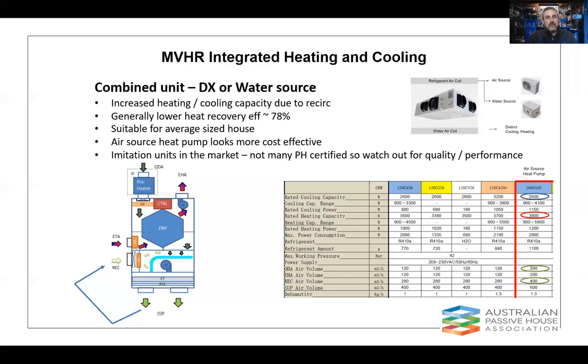Typically these products are not at the upper end in terms of heat recovery efficiency. So the unit is an all-in-one, designed to be multifunctional. Obviously with heating and cooling, the efficiency for a broad application becomes slightly less critical. But in the passive house market, equally, we're still looking ideally to get really high heat recovery efficiencies. So that said, there's a couple of these units I'm aware of that have actually reached PH certification standards, and they've got efficiencies for heat recovery in the order of 78%, which, as I said, is not at the upper end of the scale, given the better ones are approaching 90% heat recovery efficiency.